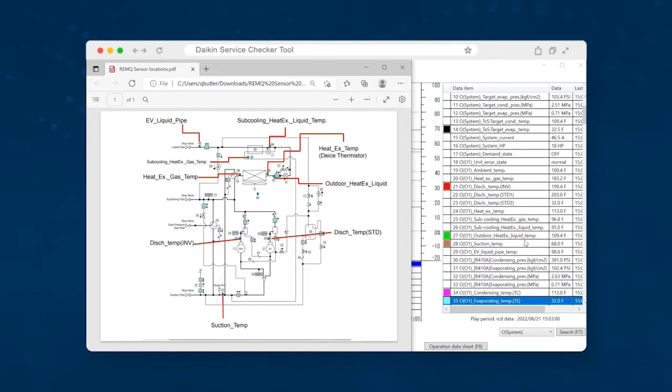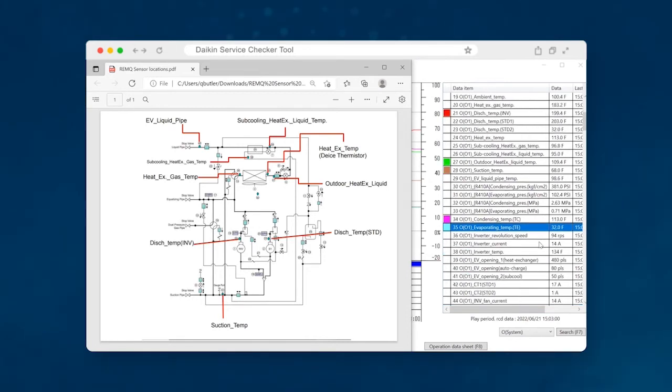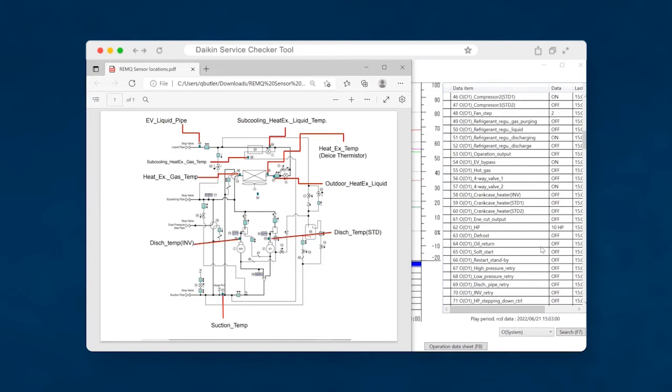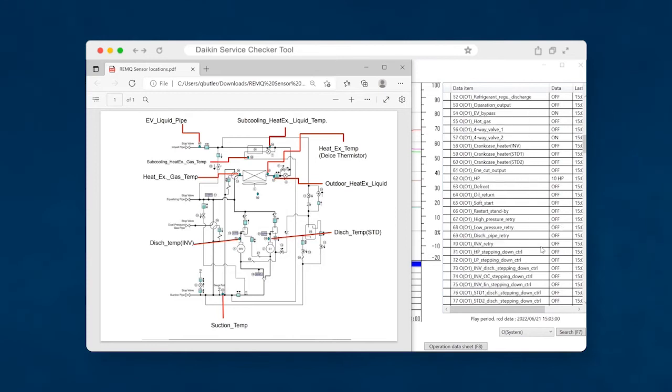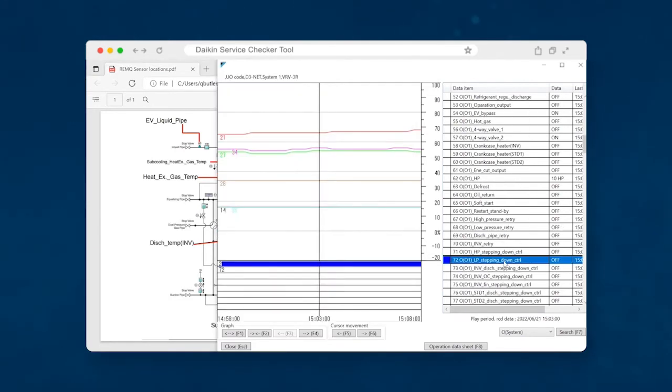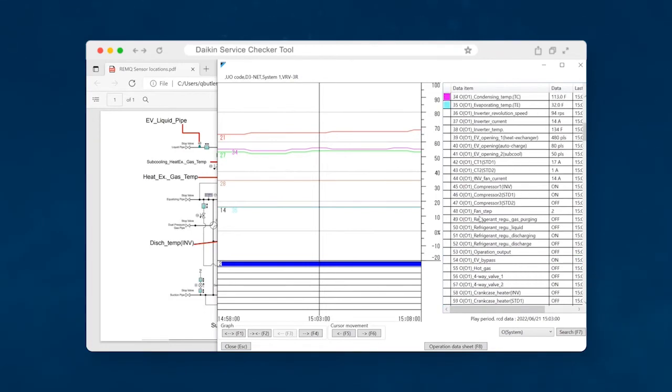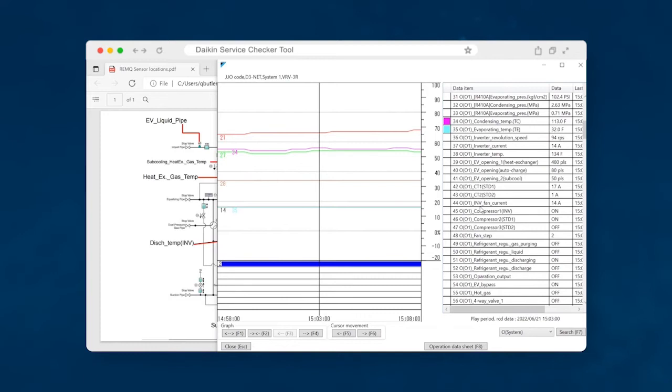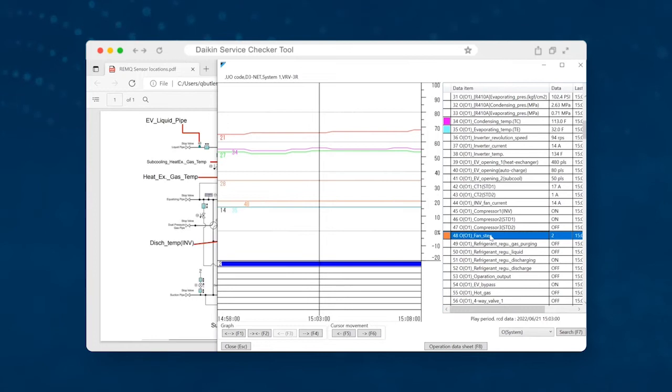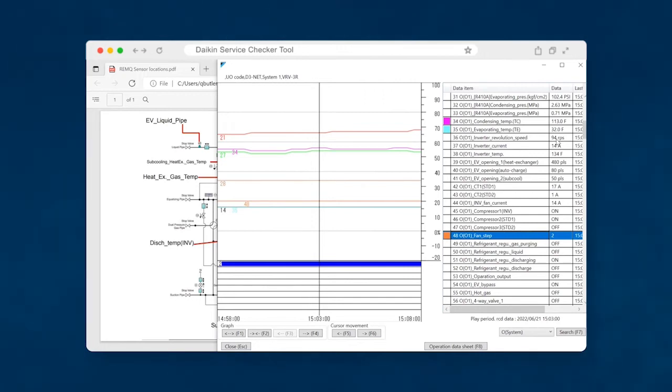One more thing that you may or may not see will be that if the system is actually recognizing that it's low on charge, you'll be able to scroll down to the safety controls. And you might see that the system is going into LP step down control, which is low pressure stepping down. Nine times out of 10, you're not going to see that unless the system is extremely low. One more piece of information that might be helpful will be your fan speed for your outdoor fans. So the fan step for a VRV3 system is going to be anywhere from one to nine. So nine being the highest, nine being the fastest.